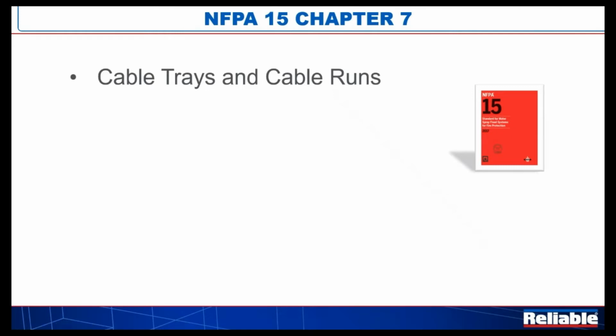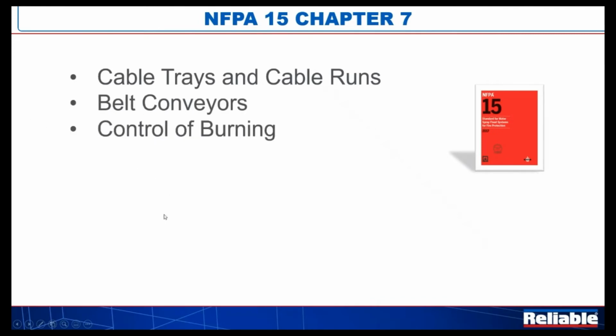Chapter 7, and again, these are not everything that can be protected or are required to be protected. These are the most common. And in a lot of cases, like we have to do with special sprinklers and special system designs, we need to extract the appropriate parts of these maybe different types of protection and apply them to whatever it is that may be new that's come across our board. So, but for these typical common protection schemes, we're going to see things like cable trays and cable runs, belt conveyors, as we talked about, an interesting chapter or section called control of burning, which we'll learn really is related to open tanks of material.